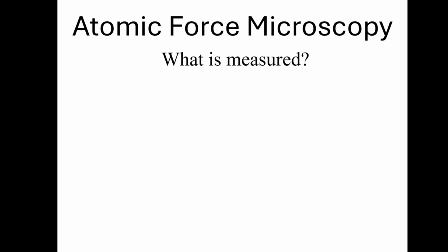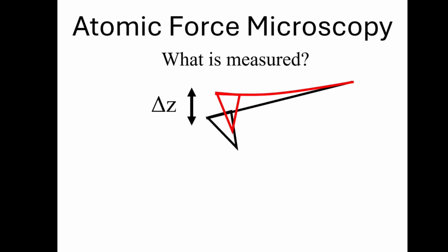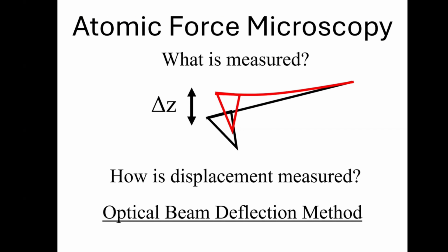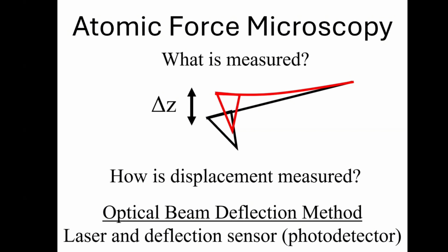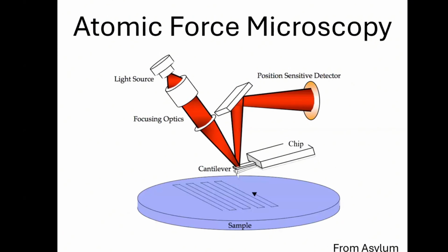So how do we do this? An easy way to think about what we are measuring is the displacement of the tip through the bending of the cantilever. But how can we measure this? By far the most common approach is called the optical beam deflection method, where a laser is reflected off the backside of a cantilever into a position-sensitive photodetector. Here we can see the basic design of an AFM. We have a laser focused on the backside of a lever, reflected into a photodetector with a mirror, and then we can move the tip or sample to trace out an image of the surface.